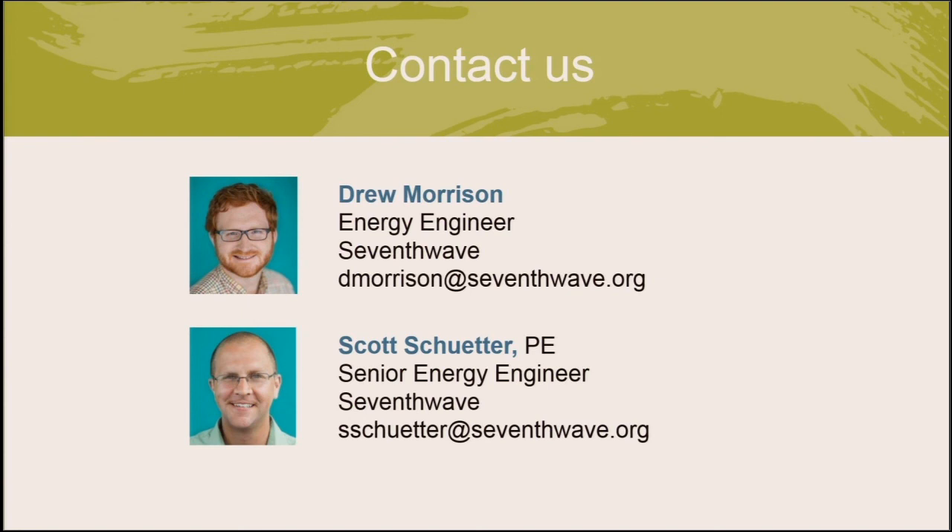Are there any settings in which PMAC motors are not recommended? An engineering cost feasibility analysis — including talking to a manufacturer's motor representative and analyzing energy savings versus an induction motor — is the best starting point. Applications where safety concerns around the strong magnetic fields are significant, or where power quality is poor, are probably places where PMAC motors would not be recommended.